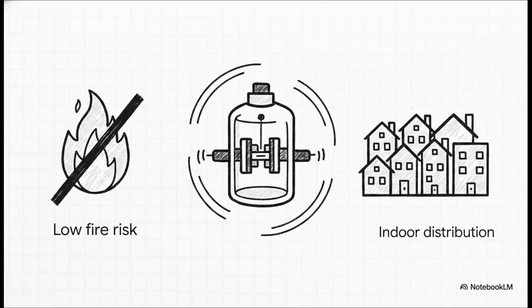But as we step down the grid, the technology shifts over to vacuum circuit breakers. By utilizing a vacuum bottle interrupter, which, remember, literally removes the medium altogether, you get near-instant arc quenching and incredibly low contact wear. And because these things don't rely on pressurized gas or oil, they boast extremely high mechanical endurance and a really low fire risk. This makes VCBs the absolute gold standard for indoor distribution networks. They're just perfectly suited for the much higher switching frequencies you typically see down in those distribution tiers, right near our commercial and residential buildings.